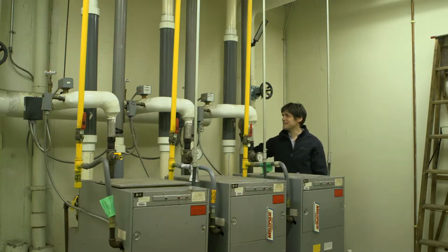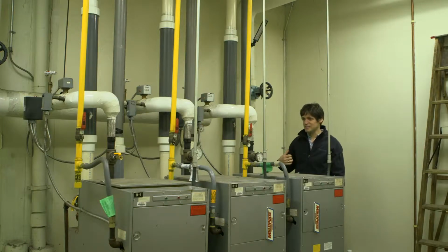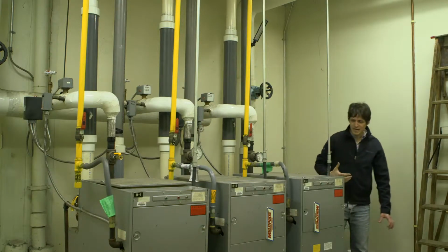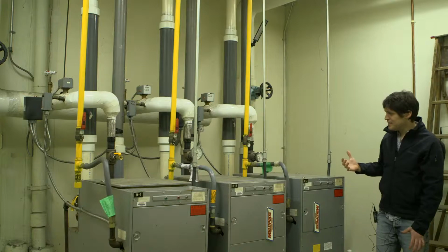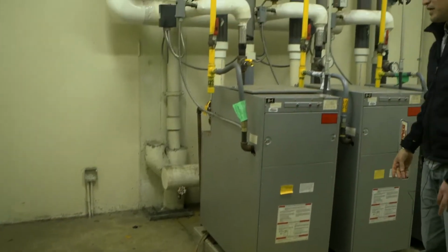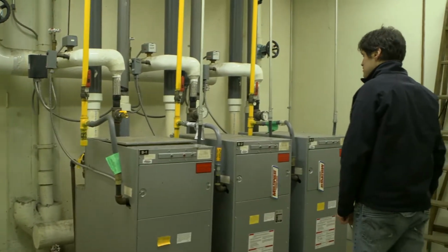These are plastic vents suggesting condensing boilers. You can also notice that there's a lot of corrosion around the drainage where this condensate comes out of the flue gas into the drainage. You see that it's corroding.